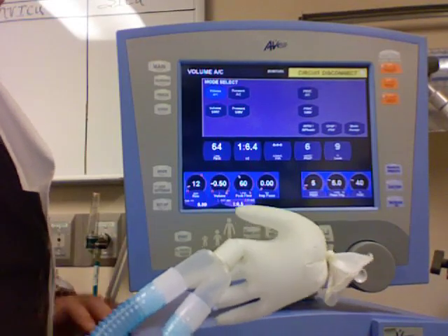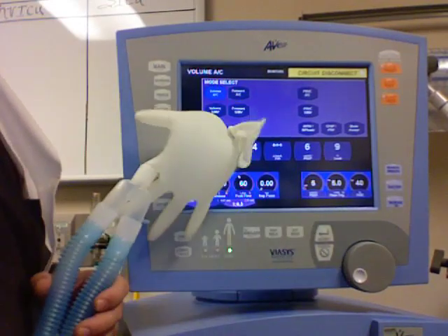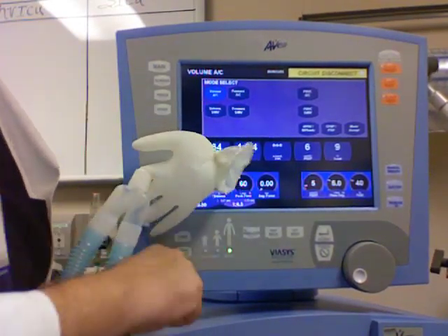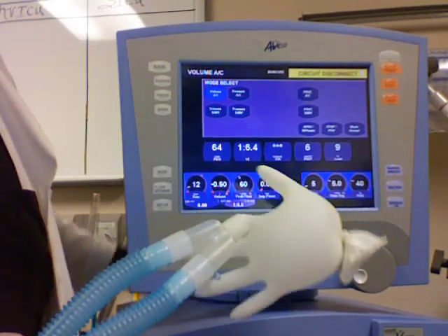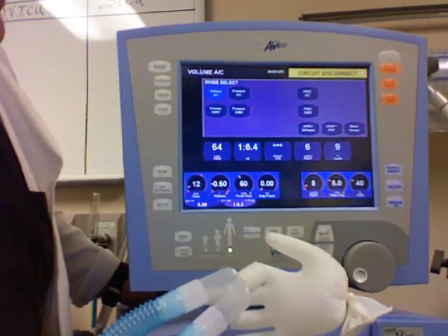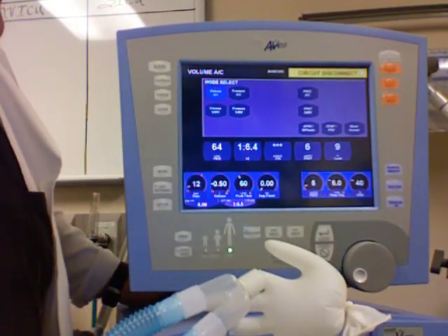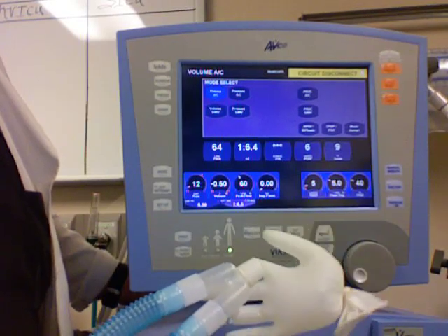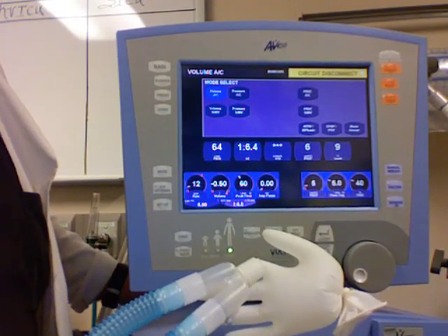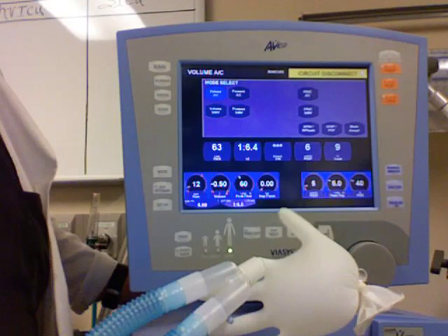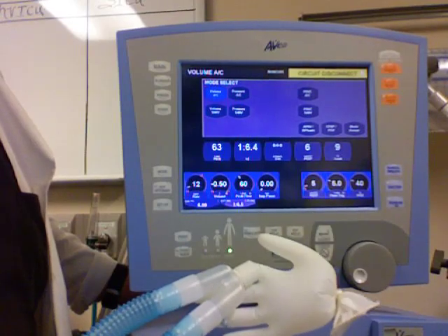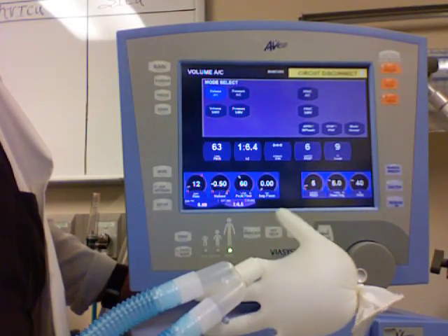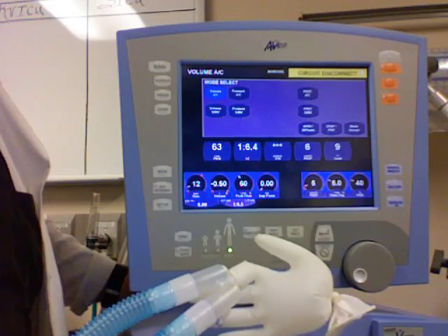There's an exhalation valve inside the machine that holds the breath until the tidal volume has been delivered. It's called an exhalation valve — kind of like what you see on your IPPB. It holds so that the pressure can build in the circuit while the 500 is being delivered, and then after the 500 has been delivered, the valve opens.